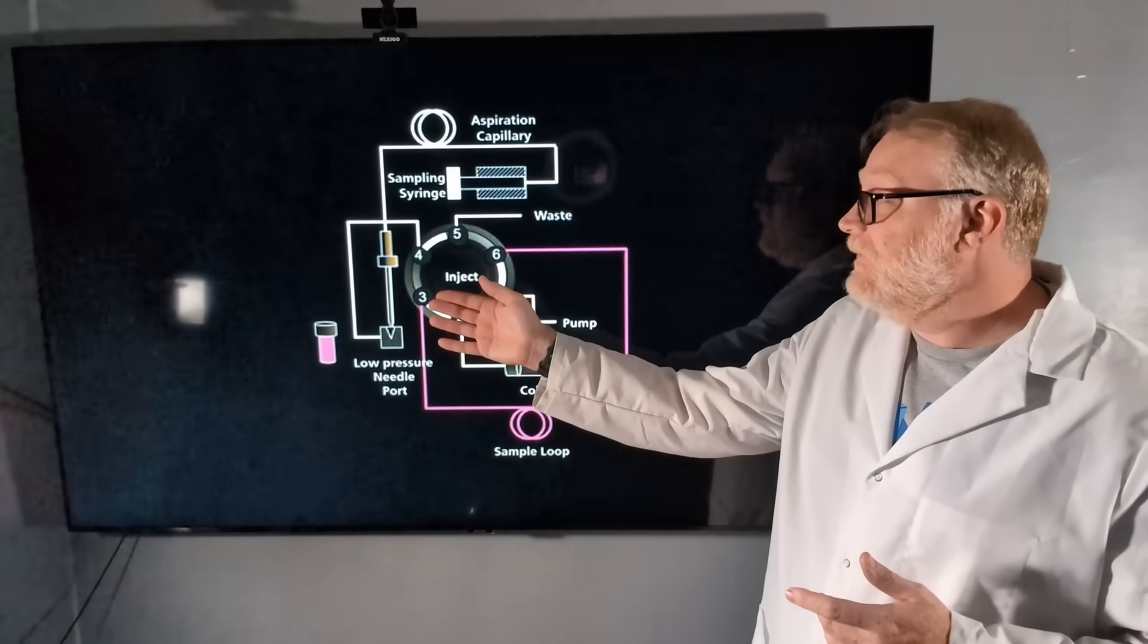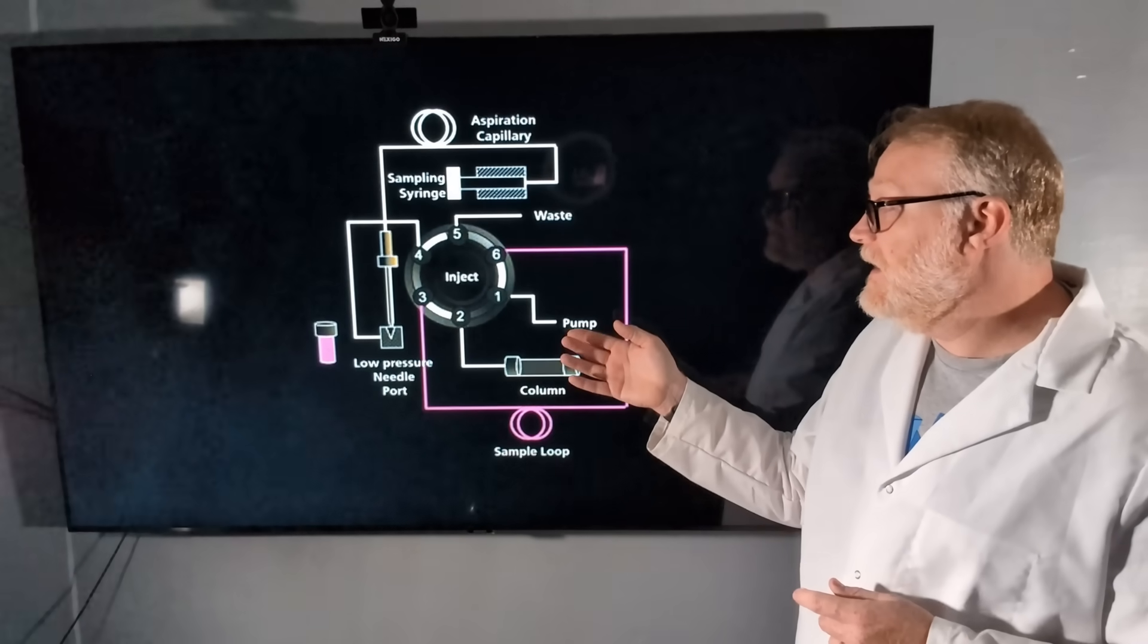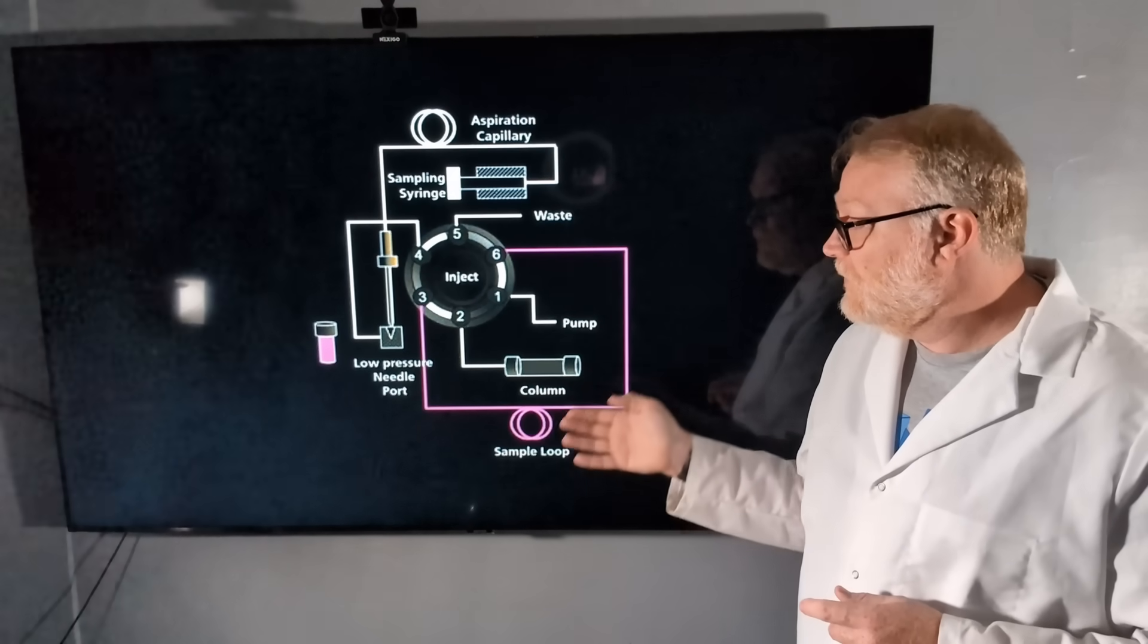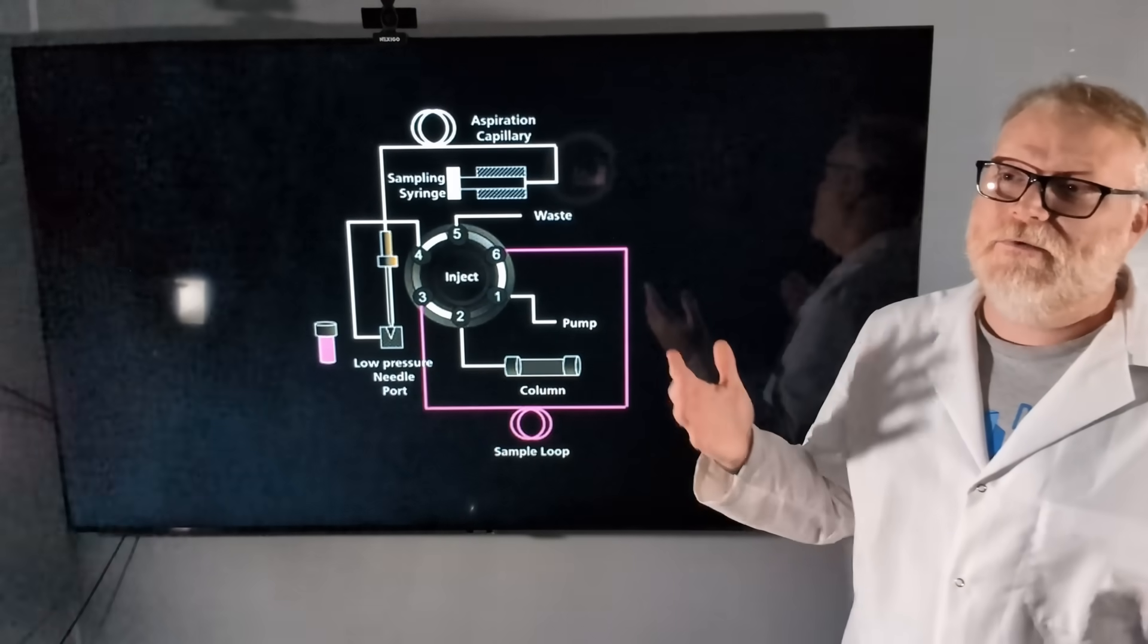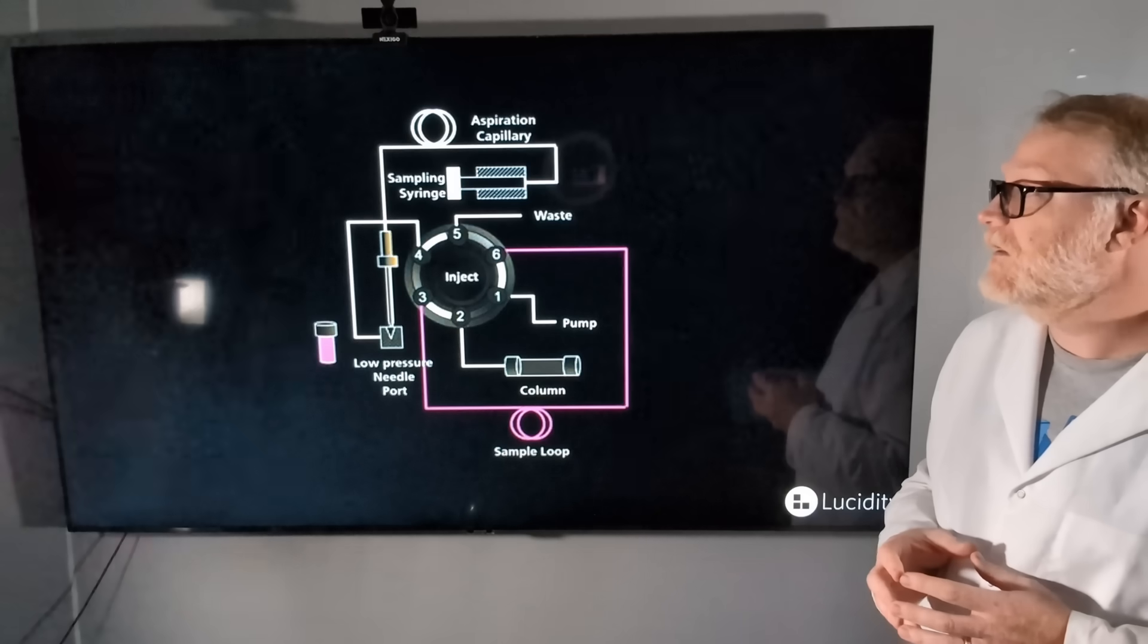Once that's completed, the valve is going to go into the inject position, and then the sample loop is now connected directly to our pump, through the loop, into our column, which will get our peaks at our detector connected on the other end of our column.